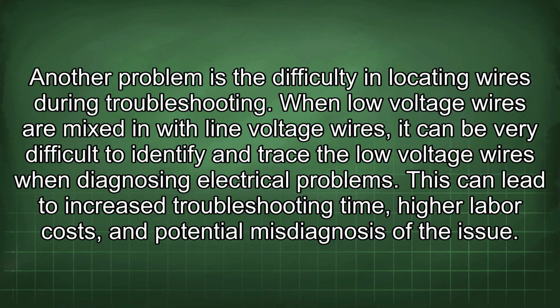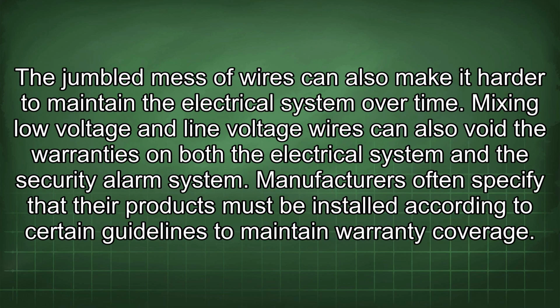Another problem is the difficulty in locating wires during troubleshooting. When low voltage wires are mixed in with line voltage wires, it can be very difficult to identify and trace the low voltage wires when diagnosing electrical problems. This can lead to increased troubleshooting time, higher labor costs, and potential misdiagnosis of the issue. The jumbled mess of wires can also make it harder to maintain the electrical system over time.